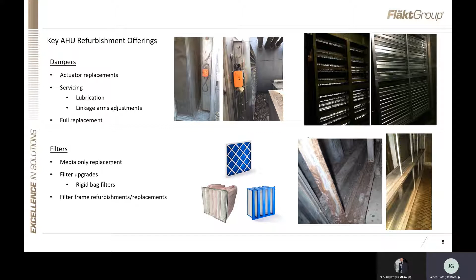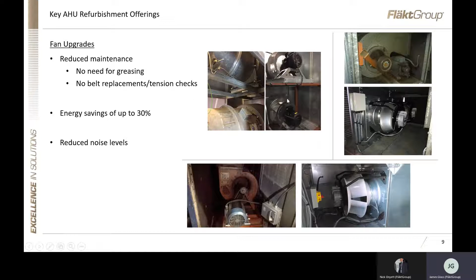Fan upgrades, again, this is something that we would look at when we're doing a survey of the air handling unit. We would consider what's inside it, look at how much it's currently costing to run, and look at the benefits the client would enjoy if they changed the old inefficient belt-driven units to a more energy-efficient EC plug fan, where applicable.